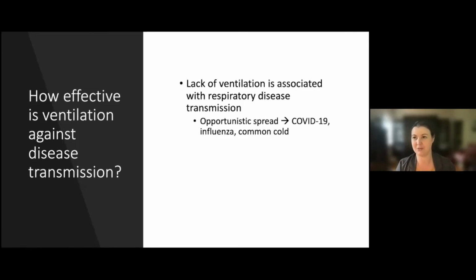Probably the best example of that is the restaurant outbreak in China last year, where they spent quite a bit of time characterizing the space and figuring out where the ventilation assets are and what the airflow is like. They determined that the fresh air ventilation rate for that particular outbreak was about 1 liter per second per person, which is way too low—basically just the fresh air that could get in through the door every time it was open.